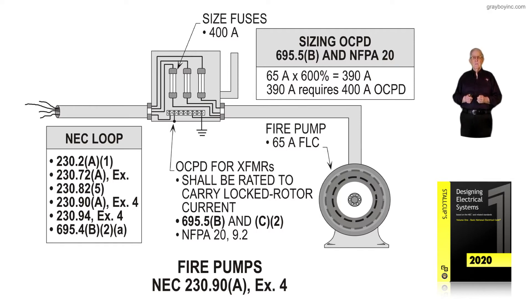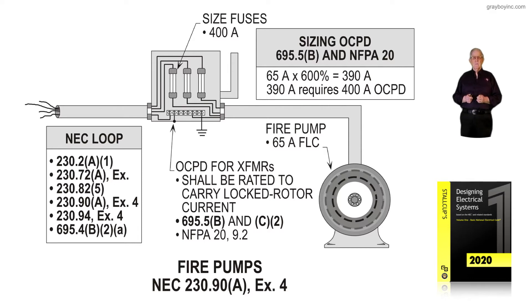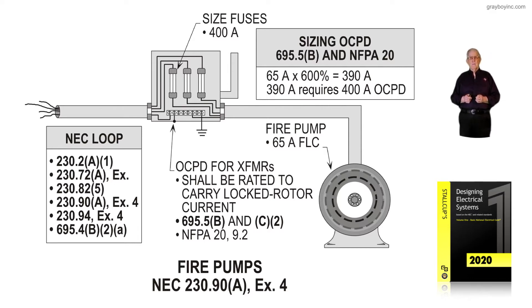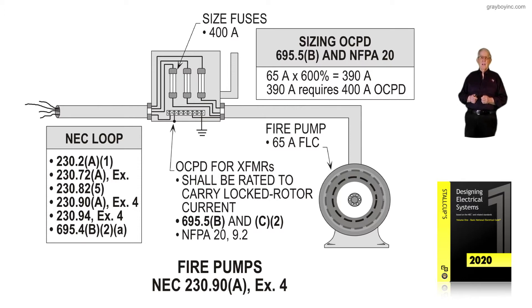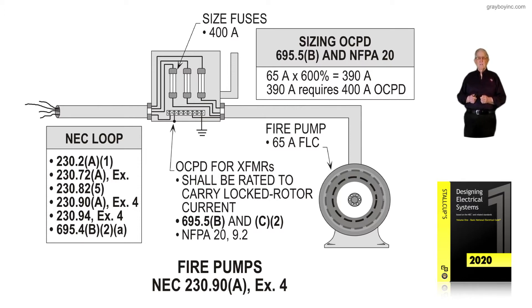That would be a 400A device. The conductor at 65A full load current would be sized at 125% of 65, so it'd be a number 4 conductor, but it'd be on a 400A device. The overcurrent device would be sized to carry that fire pump until failure occurred.